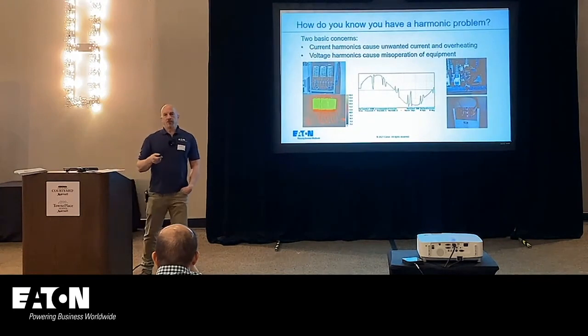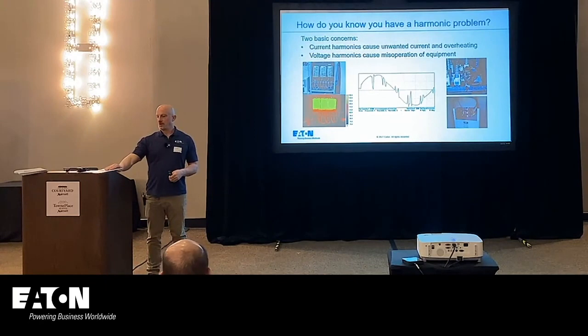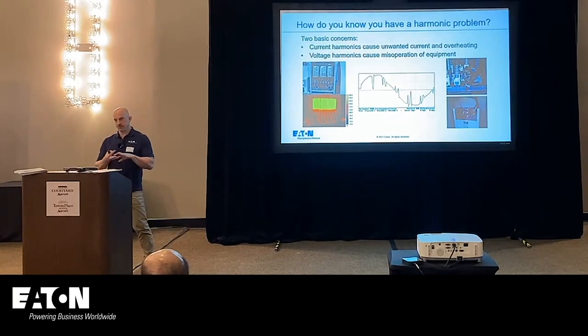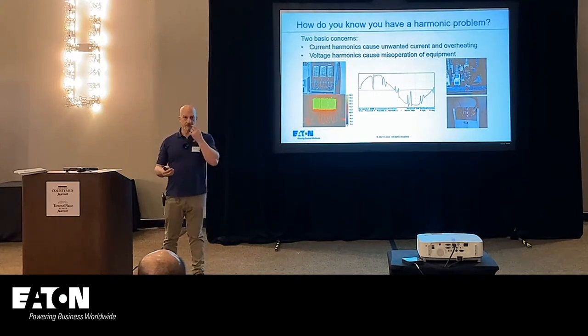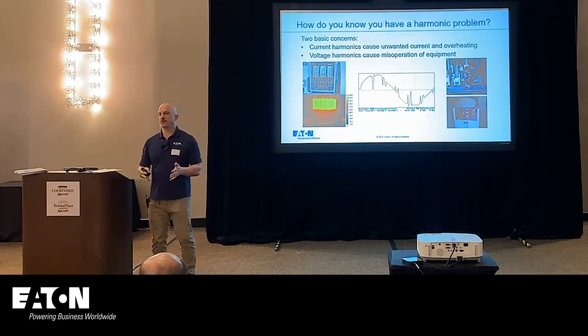So how do you know you have a problem? Okay, we're talking about solutions. So a solution implies you have a problem. Well, we talked already about it. Current harmonics, which come from the loads and push back into the system. That's our constant current source. Let's say I have a VFD, and it's a 30 horsepower drive, and it produces 10 amps of fifth harmonic current.